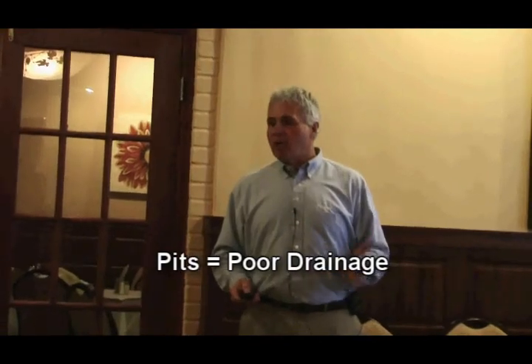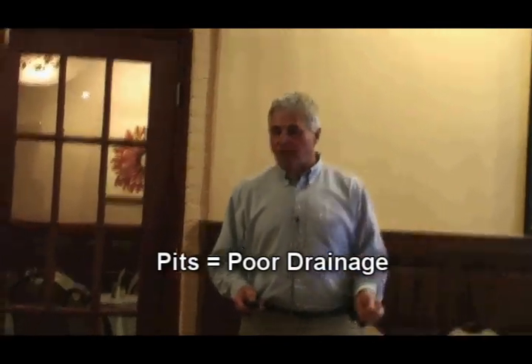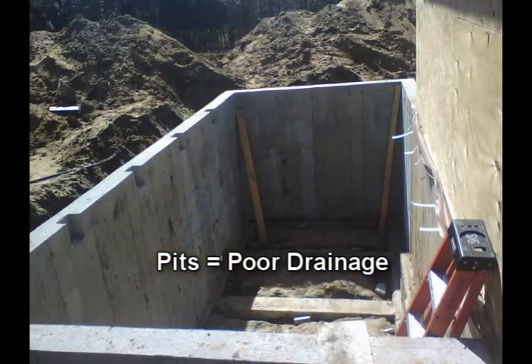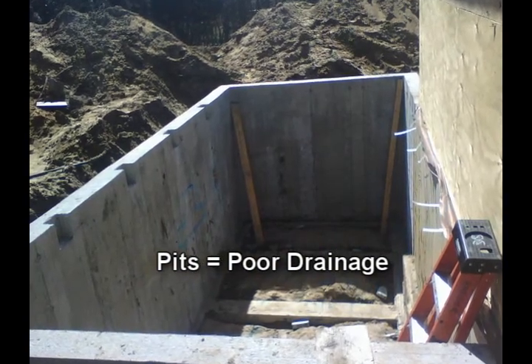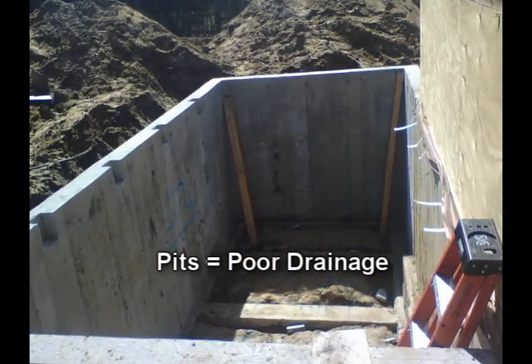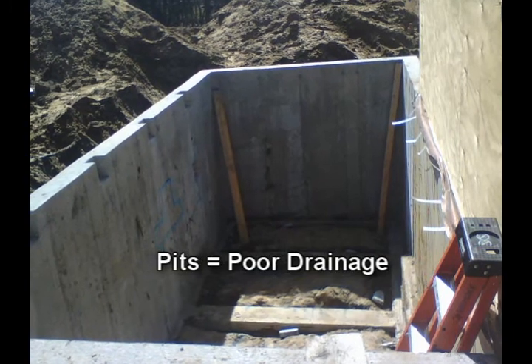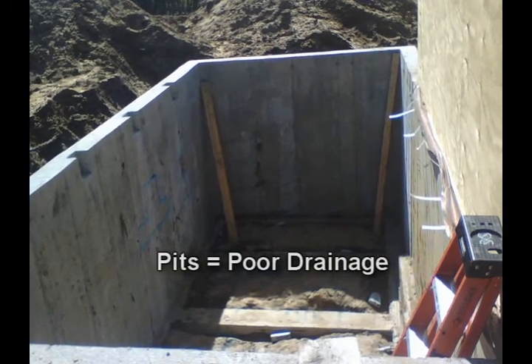First off, how do you service it? I don't know. So secondly is drainage. I can't tell you how many times the homeowner calls us and says, my generator set's not working because now it's a submarine. There's 4 feet of water in the bottom of the pit and the generator is half submerged. Whoever designed the pit did not design for proper drainage. So we discourage the use of pits. Will you find it? Yes.